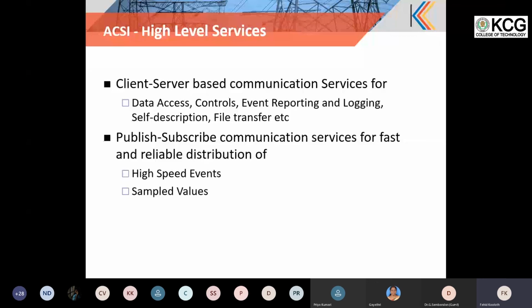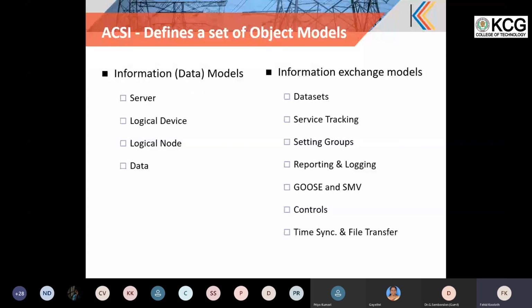Then moving on to further details. In the information model, there can be a server, then the logical device. For example, protection can be a logical device functionality. Under that you can have multiple specific protections like over voltage, over current, under current, frequency, etc. So protection can be a logical device. Under that, a specific protection is a logical node. Under that you can have multiple data.